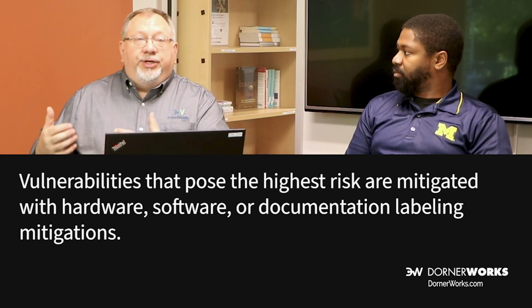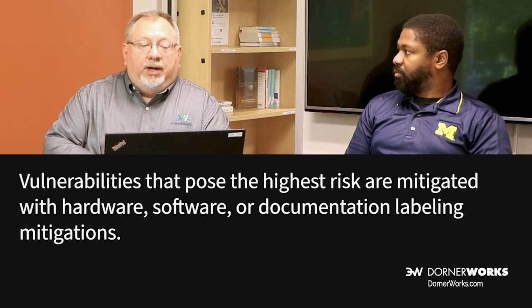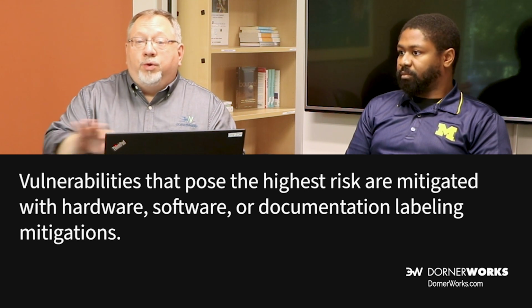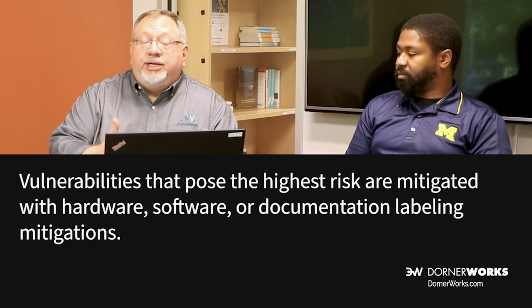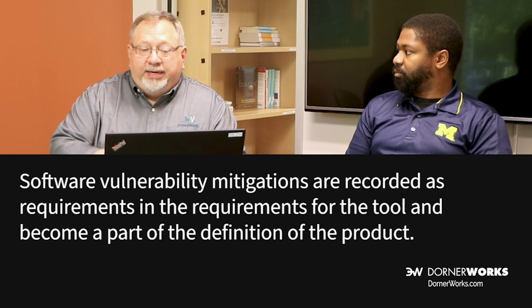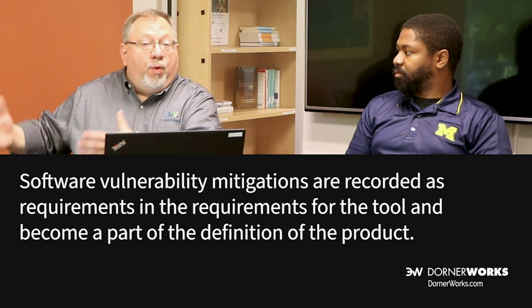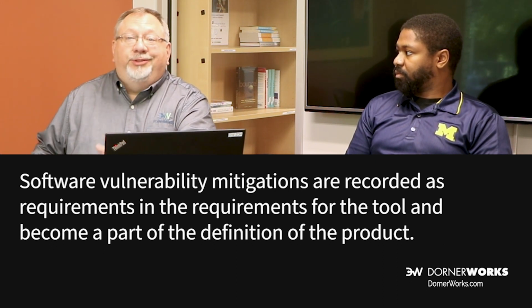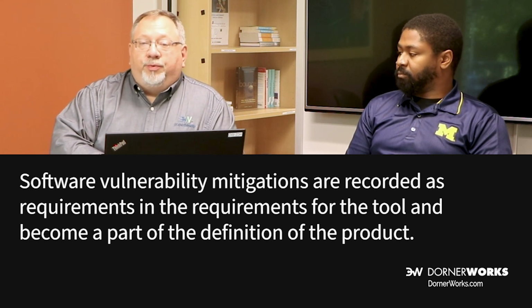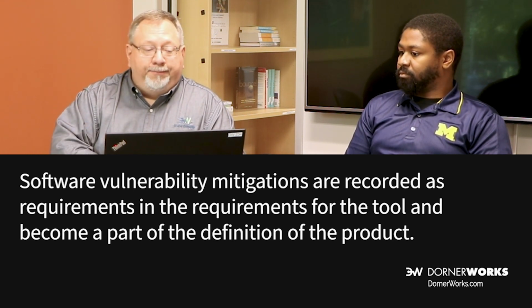Now, obviously, a labeling mitigation is the weakest of those. A hardware mitigation can be very, very strong. Totally prevent the vulnerability from occurring because you've made a change in the hardware. But software vulnerability mitigations are also done. These are recorded as requirements in the requirements for the tool. So it iterates back to the requirements, and these risk requirements then become a part of the definition of the product. So we continue to evaluate the electrical design, the software design, the architecture of the design, the code throughout the development of the process, analyzing the code for vulnerabilities, looking at the third-party components we're including and looking at the vulnerabilities that they may include.